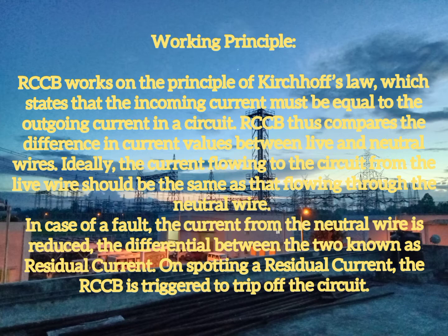RCCB works on the principle of Kirchhoff's current law, which means the current entering is equal to the current leaving. Here, the difference in current is between the line and the neutral wire. So, normally the current entering the line should return at the same level to the neutral wire.